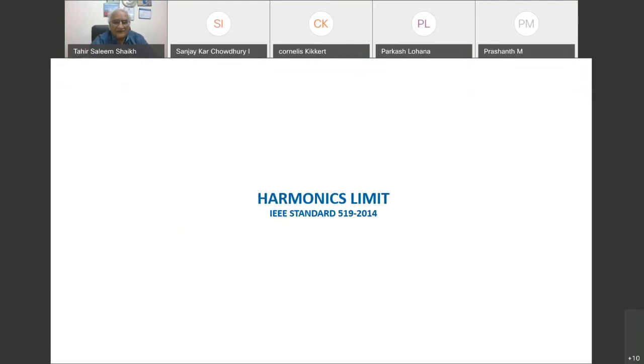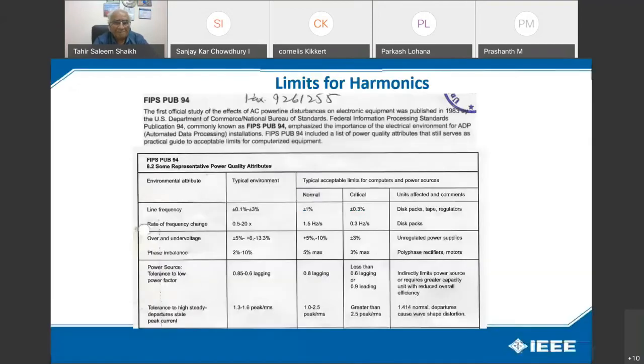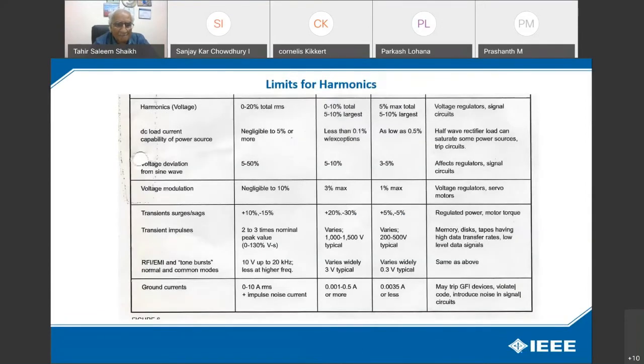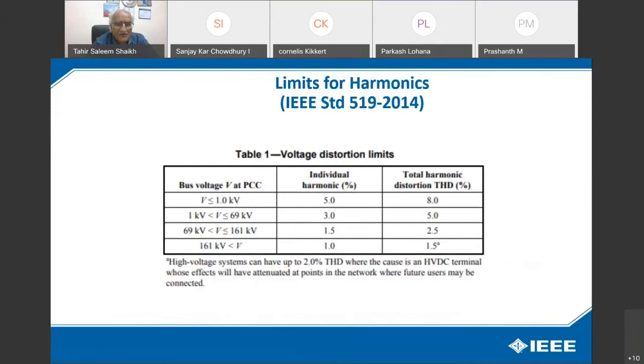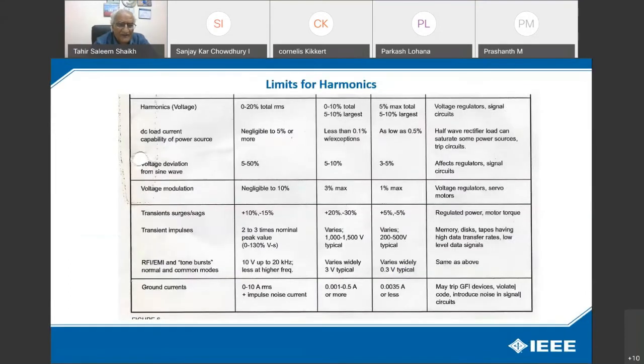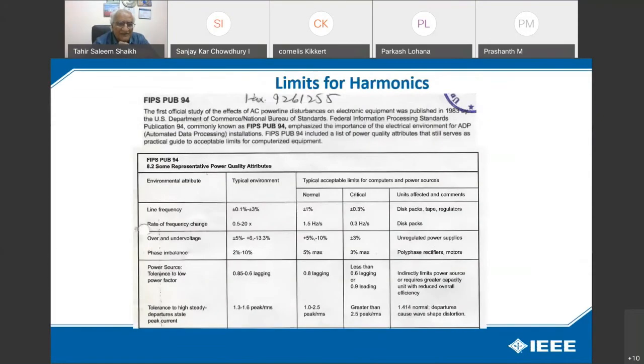Now, this is a standard for harmonic limits in IEEE standard 519-2014. You can see this chart. This gives you different environments, and in different environments, the harmonic limitations are different. So, these are the voltage distortion limits. But coming to this slide, we will discuss this. But this gives you a complete phenomenon.